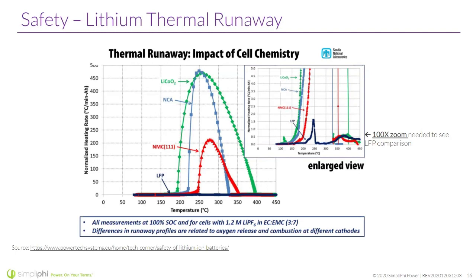What is pointed out in this graph is the change in temperature for battery cells as they go through this off-gassing event. A few slides earlier, Chuck was talking about the Note 7 and it going through thermal runaway, on a pouch cell, an LCO battery, lithium cobalt oxide. What you can see is the lithium cobalt oxide batteries will go through an off-gassing event starting around 190 Celsius.